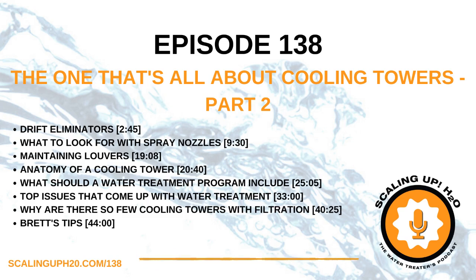I talked about that last week. Counterflow is when you have the water flowing down the fill media and the air is coming up the fill media, so they're moving counter to each other. So the water to then escape would have to turn 180 degrees and then go up with the airstream. So it's harder, right? It's got to do a complete 180 and go up. That's why your drift rates are going to be lower in counterflow type cooling towers than in crossflow.